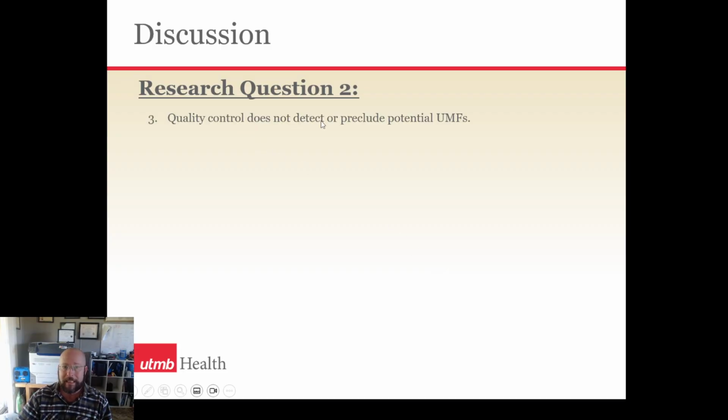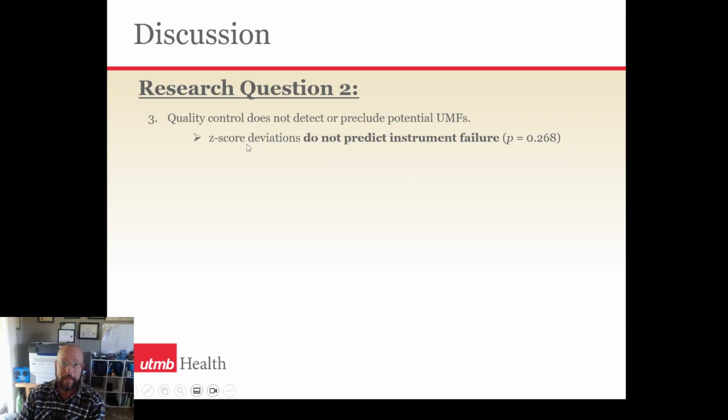Quality control does not detect or preclude mechanical failure. If you were to ask a standard laboratory what are the reasons we do quality control, they might say we want to make sure that the instrument is working appropriately. But that is not the intention of statistical quality control.